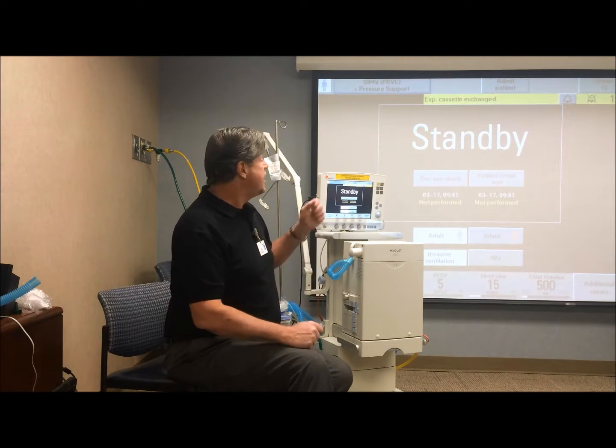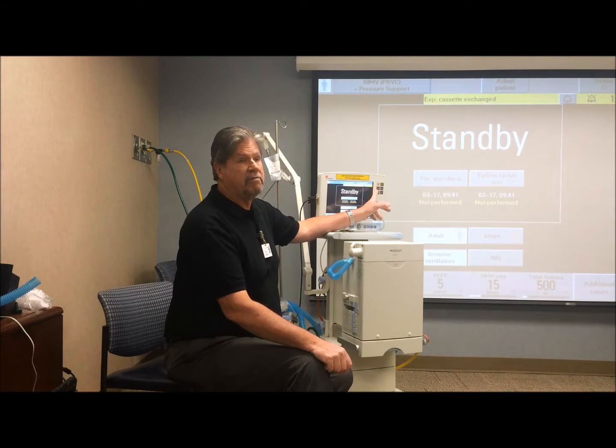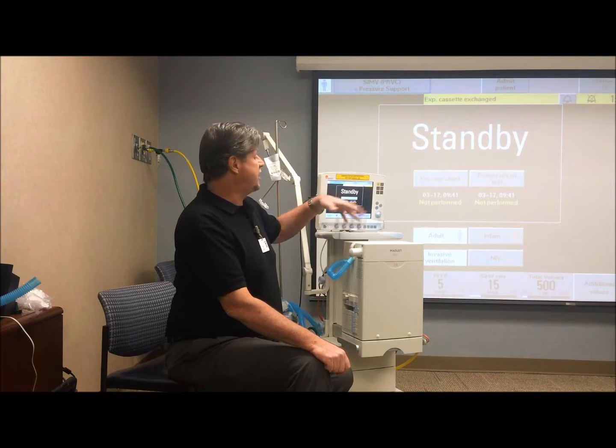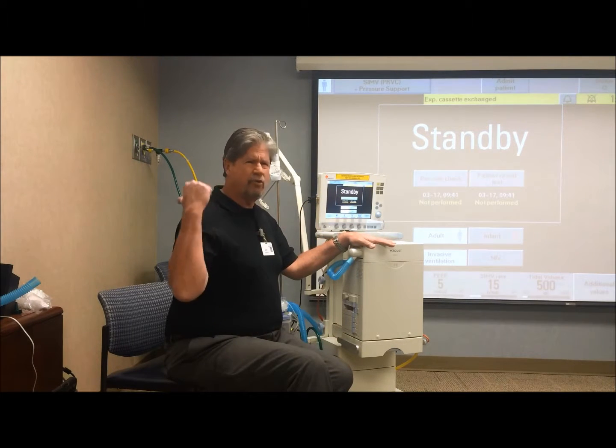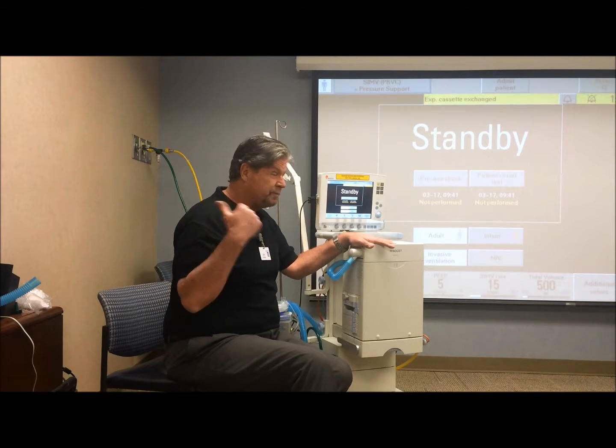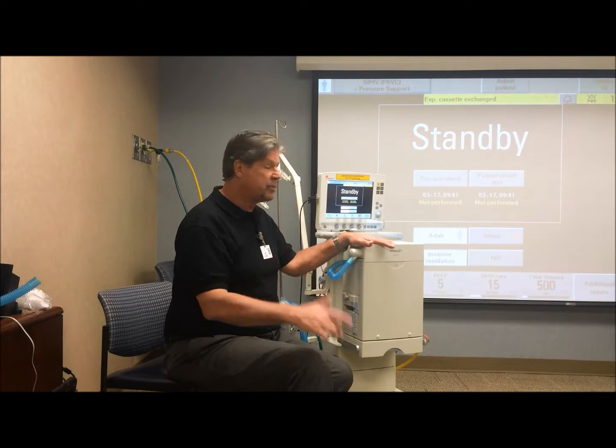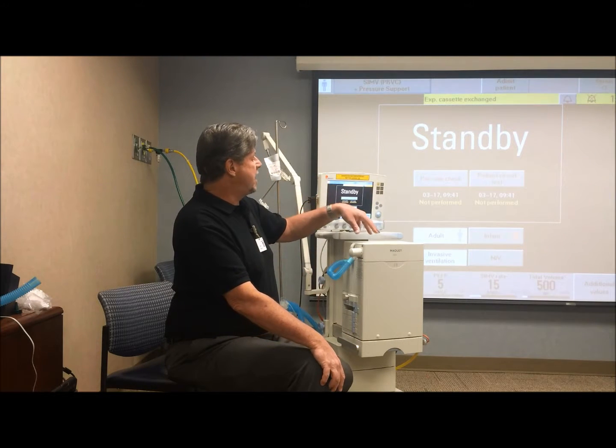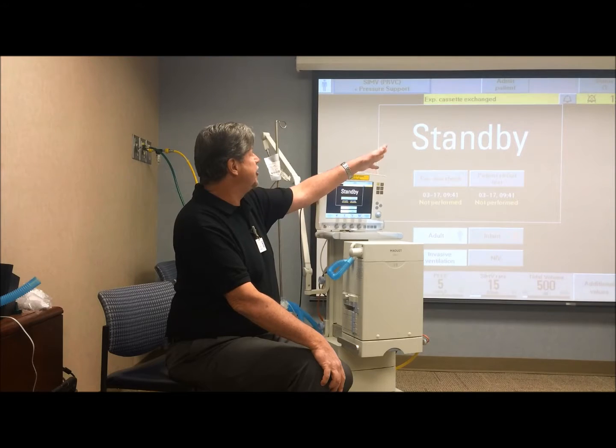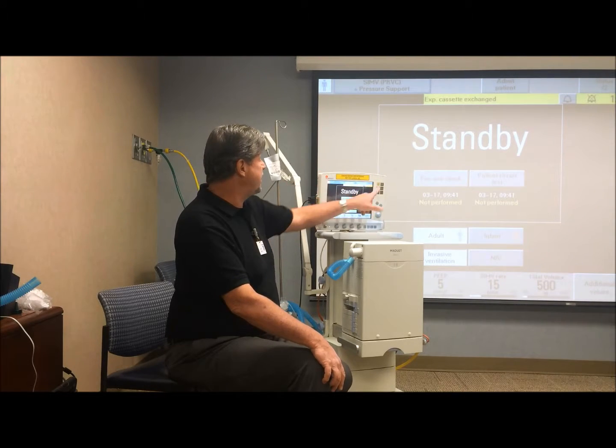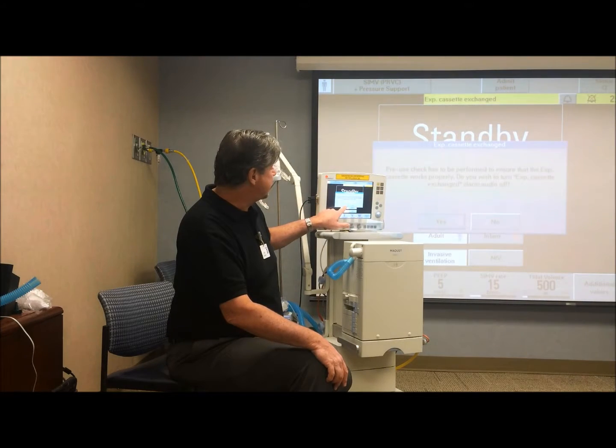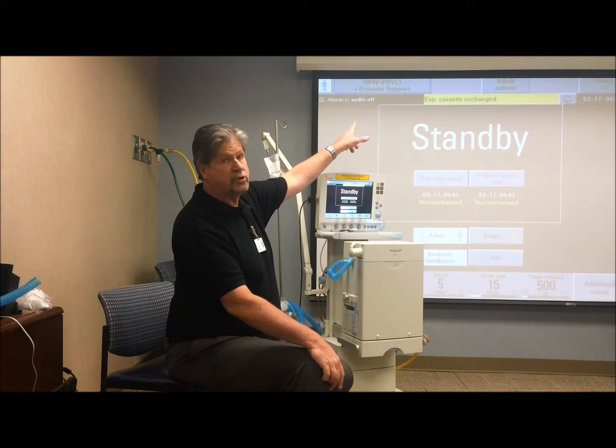If it doesn't, you can still use the ventilator, but you're telling the ventilator, look, I didn't have time, or I was in a room that only had O2, so I couldn't completely do the pre-use check. So consequently, I can't do it. So when you hit the silence button and you say, okay, yes, do you want to turn the audio off?